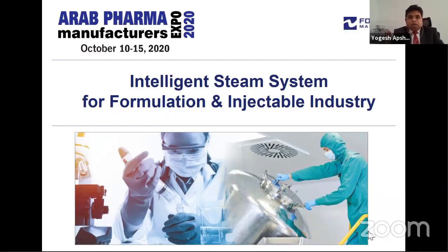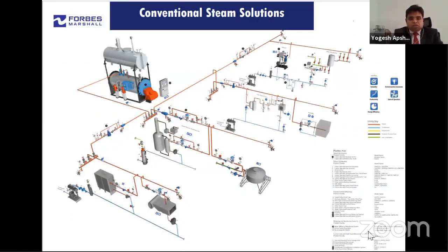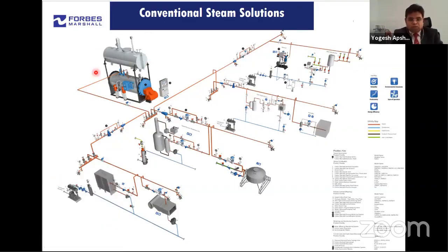So I will begin. This is how the conventional steam systems look. If you see, this is the steam boiler and the feed water. Typically we look at the steam system from a complete perspective: steam generation, then steam distribution, then utilization, and the condensate recovery. This is how a typical steam system in a pharmaceutical industry or formulation plant looks. This is the conventional steam system or the modern steam system.